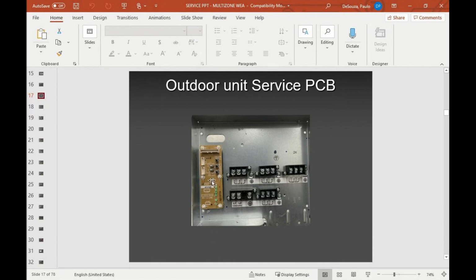And why? I have noticed, on whichever units came back mechanically damaged, I removed the compressor and there was no oil in it. So somehow oil was getting trapped and not coming back to the compressor. So remember, guys, please do not put traps. U-traps, P-traps, no traps allowed in our system. In our single zone, in our multi-zone, no intentional traps, guys. There are no intentional traps. That will just cause the compressor to die in less than 9 months, maybe even less than 6 months.